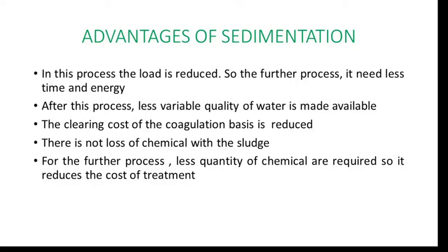In this process the load is reduced, so the further process needs less time and less energy. After this process, water of less variable quality is made available. The cleaning cost of the coagulation basins is reduced. There is no loss of chemical with the sludge, and for the further process, a smaller quantity of chemicals is required. So it further reduces the cost of treatment. These are the various advantages of plain sedimentation before the process of coagulation.